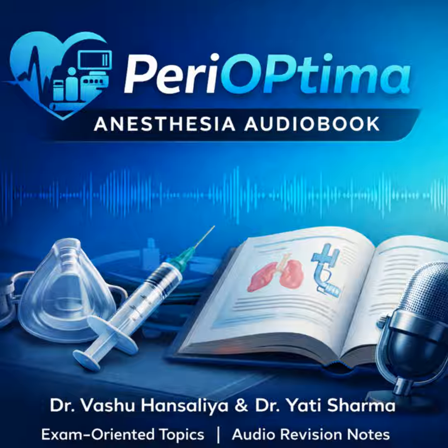It requires a higher flow, maybe 1.5 to 2 times MV, because that long tubing allows for more mixing and rebreathing. So it's extremely common. Extremely common, especially in its modified coaxial form, which is the Bain circuit. It's ideal for controlled ventilation and for transport or remote locations because it has so few components. Which brings us to Mapleson E and F.